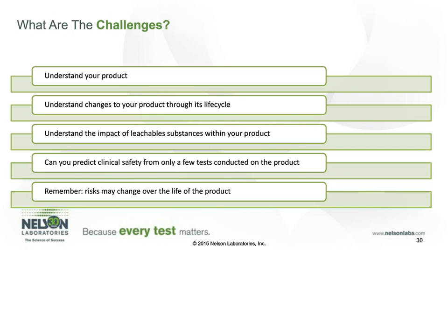Then you have to understand the changes that may happen to that product through its life cycle. One of the things I always talk about is accelerated aging or sterilization. What impact does aging have on a device? Maybe nothing on certain materials, while other materials may age poorly. Or sterilization: radiation may have a big impact on certain materials. So a material may be safe, and may have plenty of biological data done on the raw material, but that's before any sterilization has been done. We need to evaluate what impact sterilization, or repeat sterilizations, may have on a certain material.